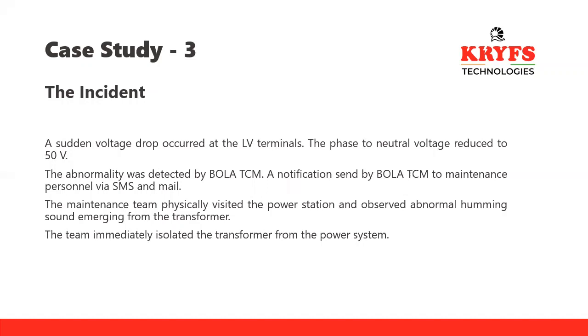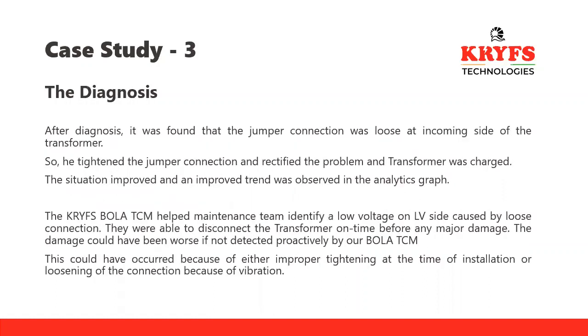Our maintenance team then physically visited the substation and observed a humming sound emerging from the transformer, and the team immediately isolated the transformer from the power system. After diagnosing the issue, they found a loose connection within the jumper connections on the HV side. They tightened the jumper connections and rectified the problem, then charged the transformer with the proper inputs, and normal operation of the transformer resumed after rectification.